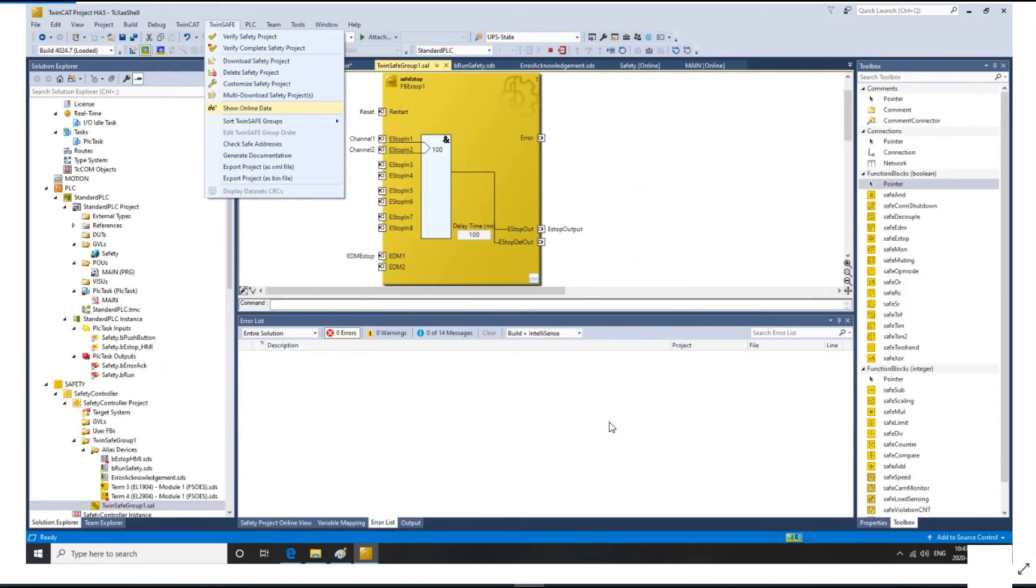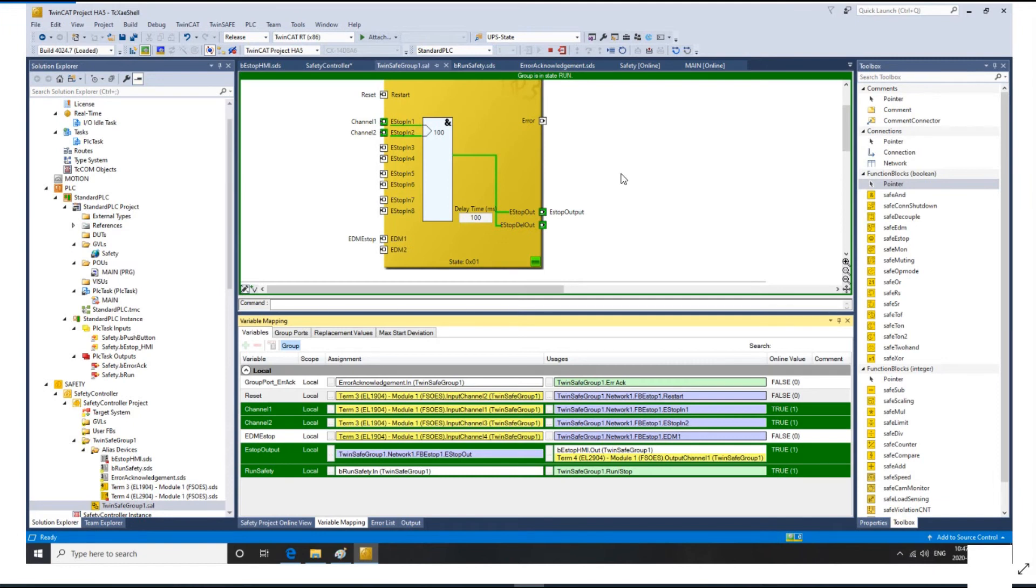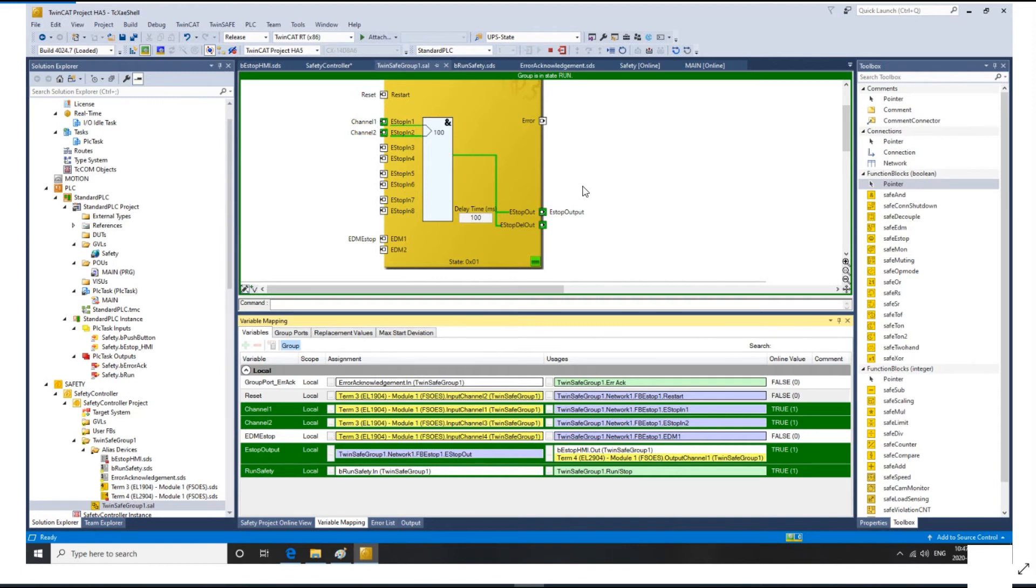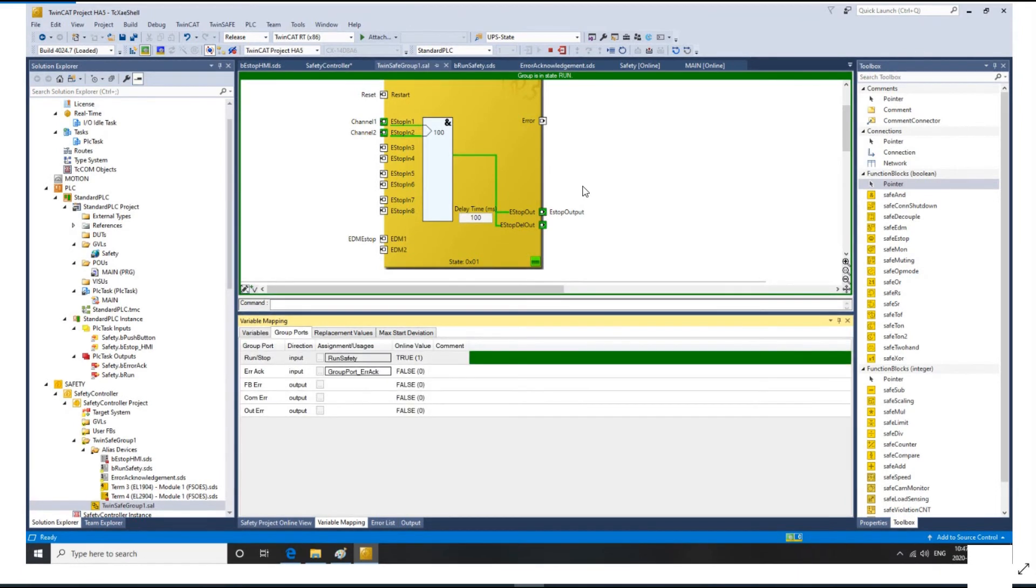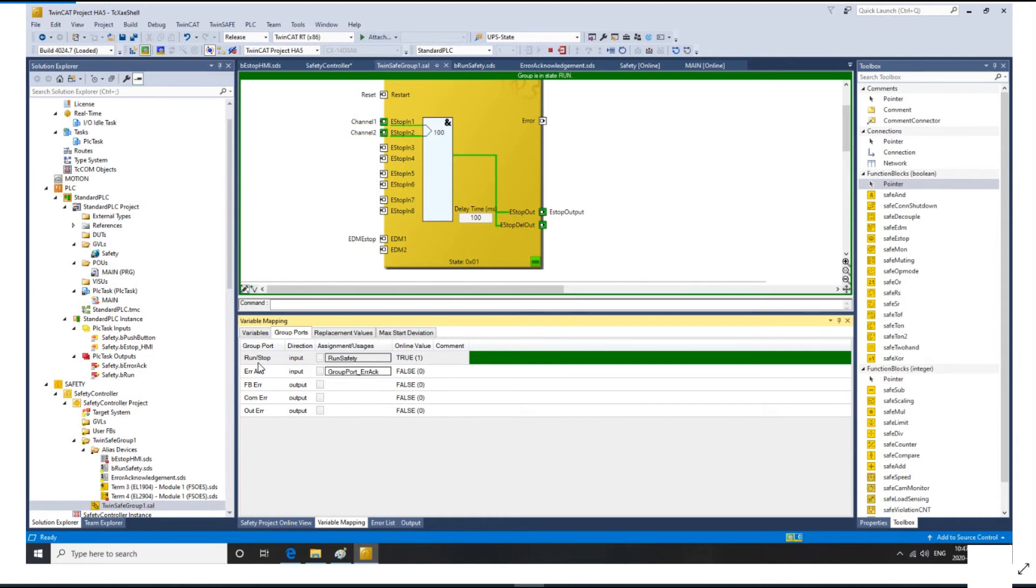After the download, if we need to go online, go to TwinSafe, select show online data. This is a specialty for the safety logic. Once the safety logic goes online, if the signal goes on, we will see the flow in green color. With this green color in that logic chart, it's easy for us to do commissioning and troubleshooting. If there's no green showing in your chart, make sure you check the run and stop signal to see if the PLC already started this safety controller.